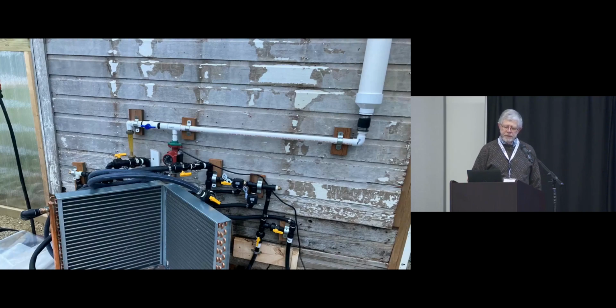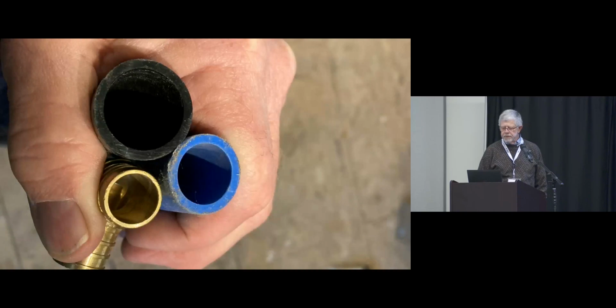One of them is that the geothermal line, which is the black line in my hand there, has an inner diameter that is quite a bit more than a 3/4 inch PEX line. And then the brass fitting is a 3/4 inch PEX fitting, which goes inside the PEX line. The geothermal lines are butt fused, and so there are adapters or fittings that go over the outside of the geothermal line. So the geothermal line is technically 3/4 inch, but it's closer to 7/8. And when you fuse a fitting on the outside of that, you're not occluding the flow. So it being already a bigger diameter, I realized I should have stepped up a size when I came off the geothermal.